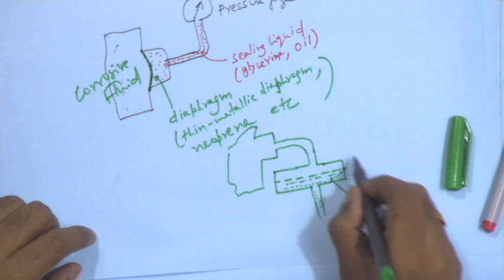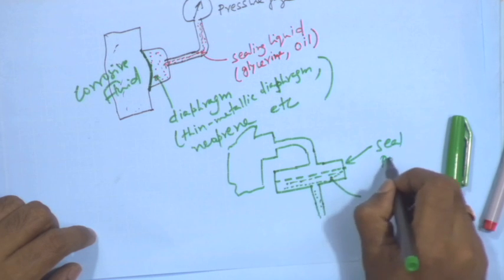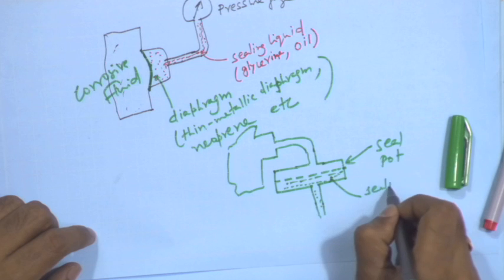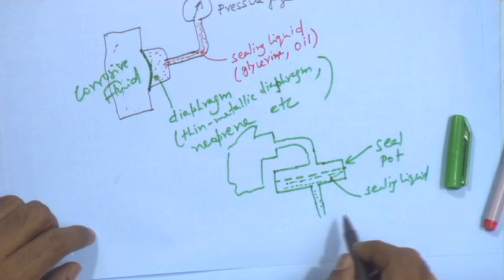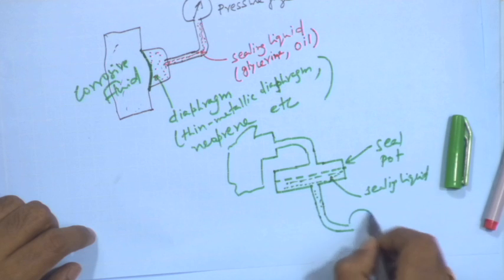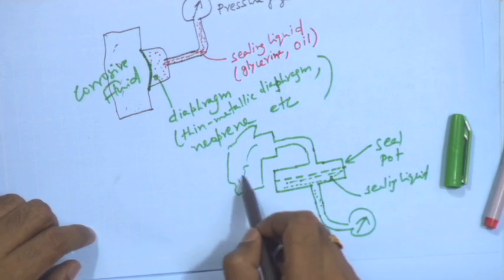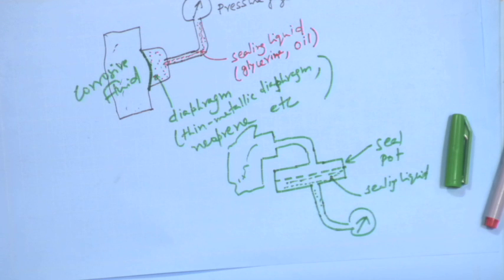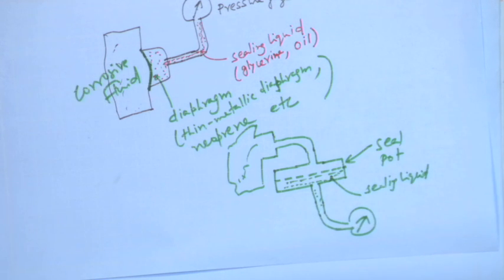So, you have a sealing liquid, you have a seal pot, this is the sealing liquid. This is the pressure gauge and this is the corrosive fluid. So, again the corrosive fluid is not being allowed to come in direct contact with the pressure gauge. So, either with help of a diaphragm element or a liquid seal, we can protect our pressure gauge when we use it for measurement of pressure of corrosive fluid.